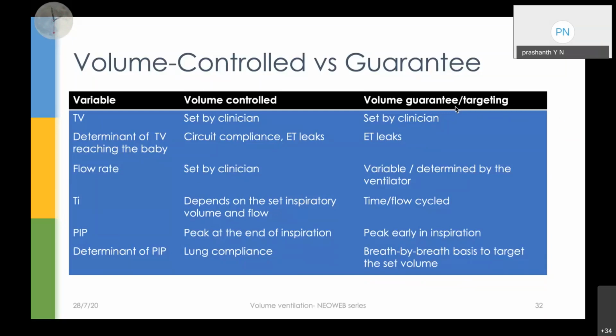So what determines the peak inspiratory pressure? In volume control, we saw in one of the graphs that the peak inspiratory pressure is achieved at the end of inspiration. In volume guarantee, the peak is achieved a little early in the inspiration itself. So it's not a jerky kind of pressure which is working in volume guarantee. Here the determinant of the peak inspiratory pressure is the lung compliance in volume control, but in guarantee it is done dynamically with each breath to reach the target tidal volume. All right.